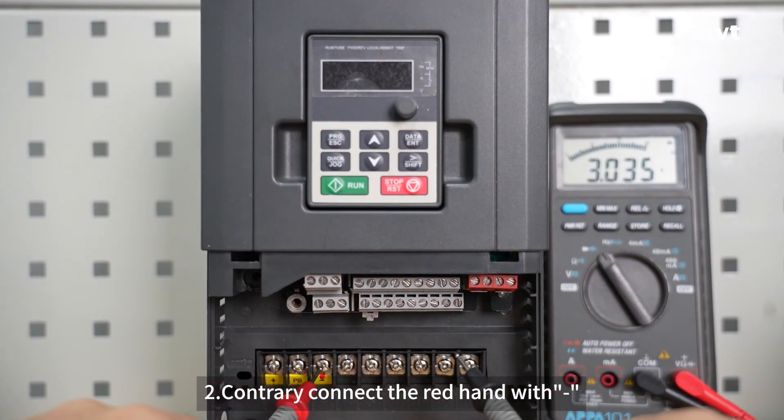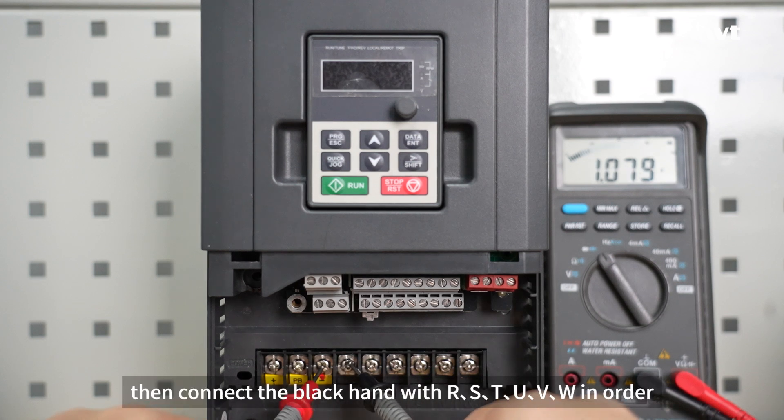Second, contrary to the first test, connect the red probe with minus. Then connect the black probe with RSTUVW in order.